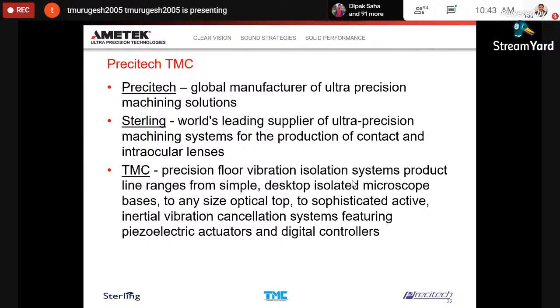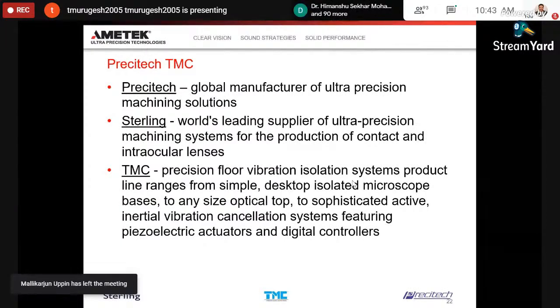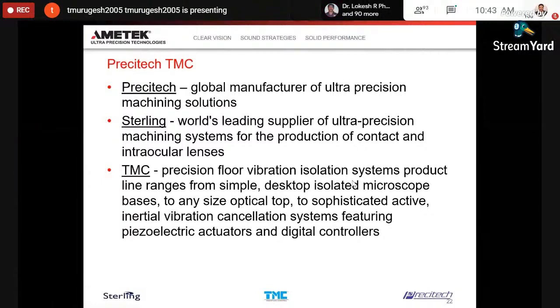I believe that being an engineering college, you might have some optical benches, or scanning electron microscopes or transmission electron microscopes, where you might have been using a vibration isolation table. I'm not sure what brand, but TMC, being an ISO 9000 certified company, produces one of the best, or global leaders, in floor vibration control systems. Name it: a confocal microscope or any very high resolution microscope. It can be an electron microscope, SEM, TEM, or STEM application, where if there are floor vibrations, you don't get the imaging.